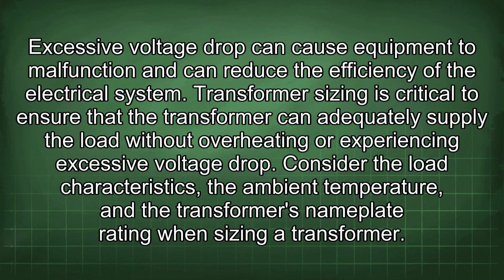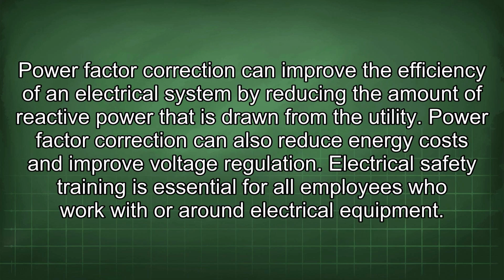Transformer sizing is critical to ensure that the transformer can adequately supply the load without overheating or experiencing excessive voltage drop. Consider the load characteristics, the ambient temperature, and the transformer's nameplate rating when sizing a transformer. Power factor correction can improve the efficiency of an electrical system by reducing the amount of reactive power that is drawn from the utility. Power factor correction can also reduce energy costs and improve voltage regulation.